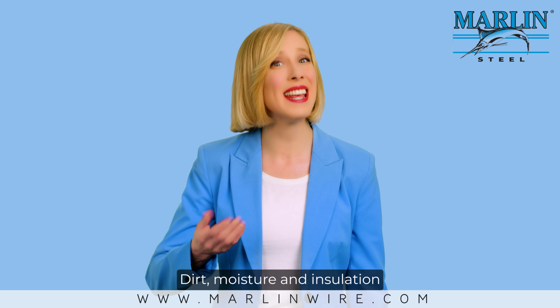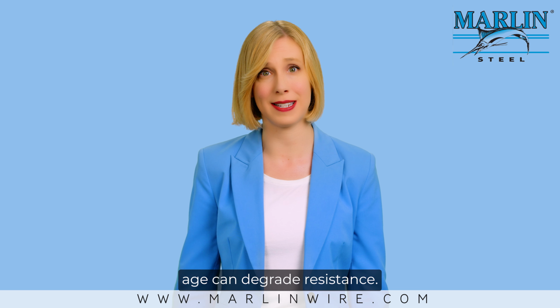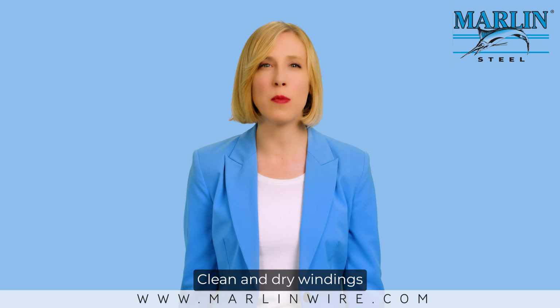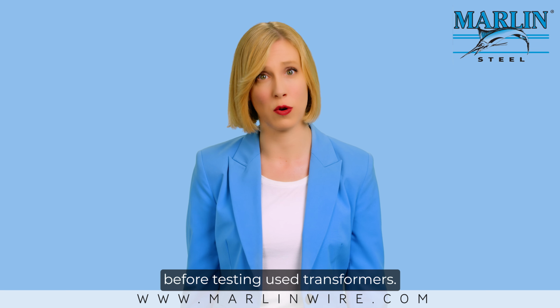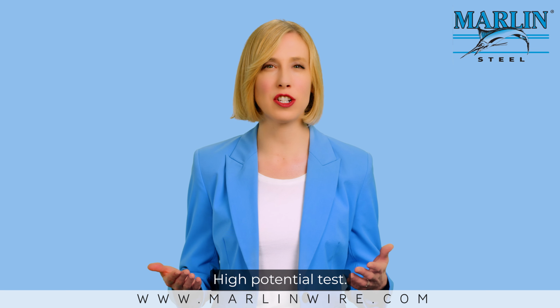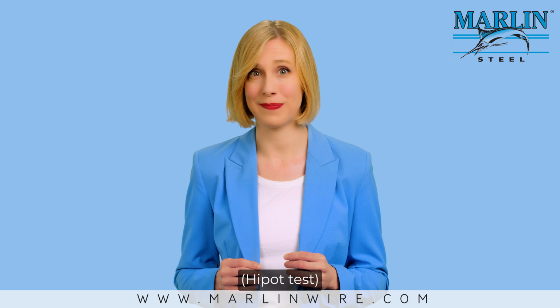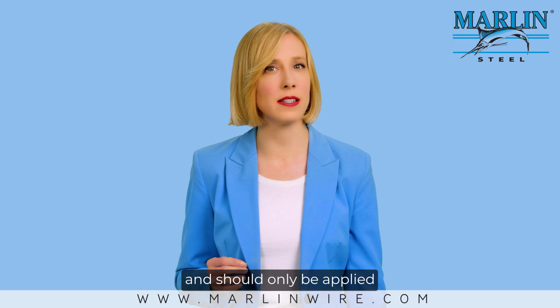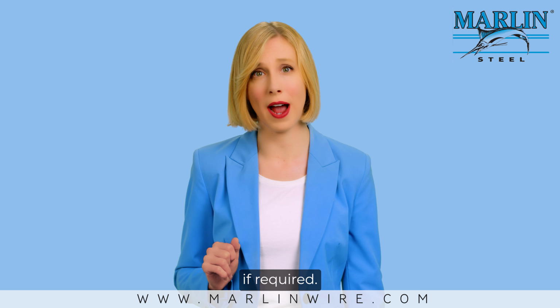Dirt, moisture, and insulation age can degrade resistance. Clean and dry windings before testing used transformers. High potential test, high pot test. This is a destructive test and should only be applied if required.